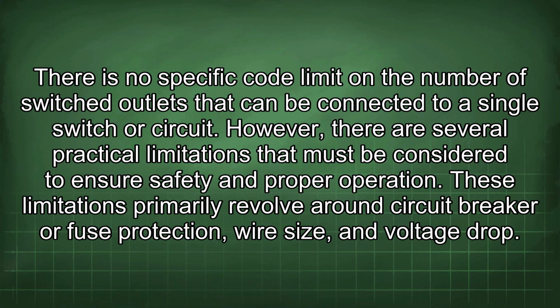There is no specific code limit on the number of switched outlets that can be connected to a single switch or circuit. However, there are several practical limitations that must be considered to ensure safety and proper operation. These limitations primarily revolve around circuit breaker or fuse protection, wire size, and voltage drop.